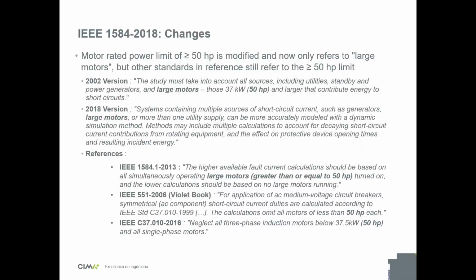So it still says large motors, and then the new standard refers to IEEE 1584.1 that still has the 50 HP limit. It refers to the Violet book that still has the 50 HP limit, and it refers to the C37.010, which still considers the 50 HP. So all in all, they removed the text, but all the references still say it's 50 HP. So this, we consider it that it has been maintained.